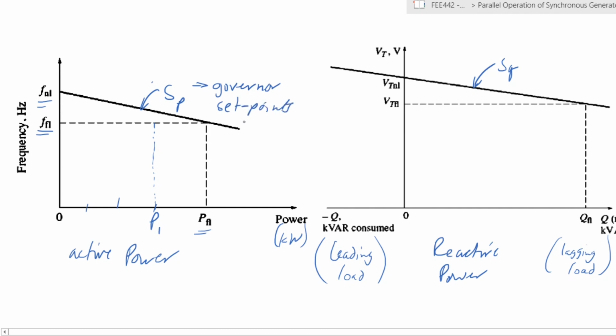Under the set points that we give in this, that result in this slope, your full load power will be at a frequency of here, FFL. But if you still want to have that frequency, but supply active power at a lower level or even at a higher level, you would then need to change the set points, and you would have a line that goes slightly like that. Okay, my line is not very accurate. Try again.